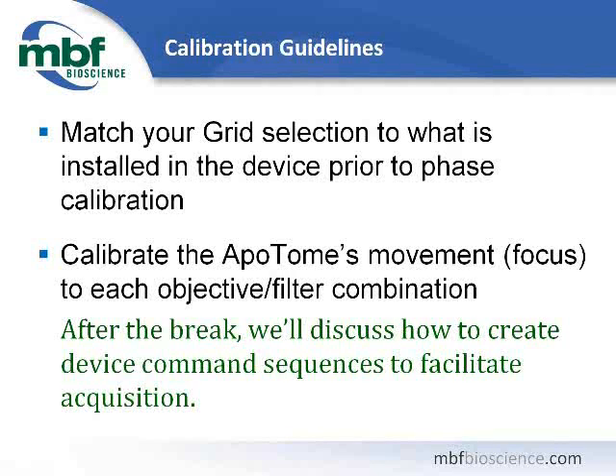That's the basics for calibration. To summarize, make sure the grid selection in the software is matched to what is installed in the device prior to phase calibration. Additionally, you need to calibrate the ApoTome's movement and focus to each objective-filter combination. After the break, we're going to discuss how to create device command sequences to facilitate acquisition.